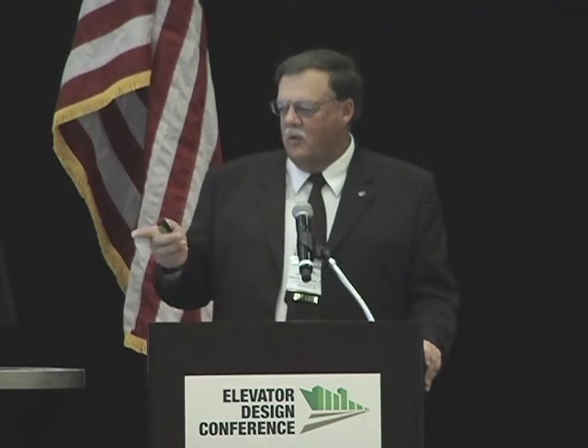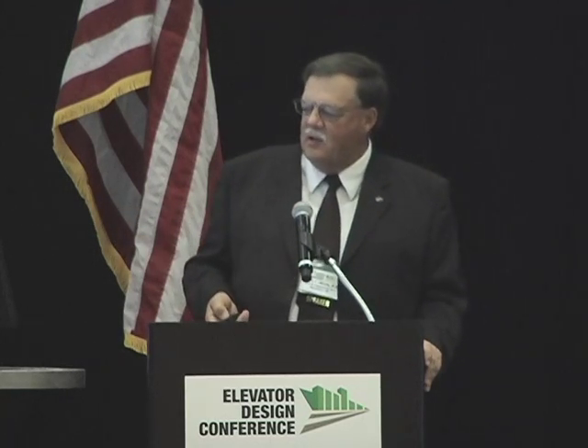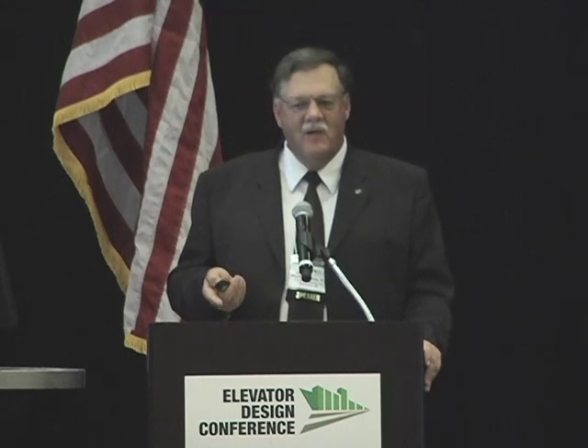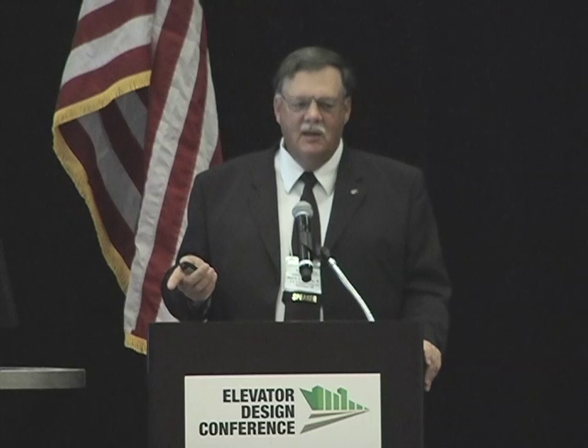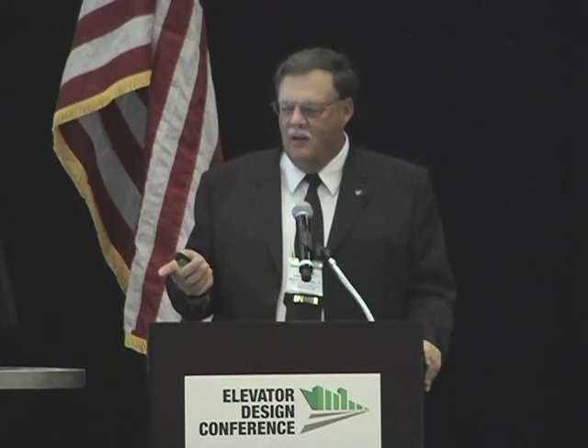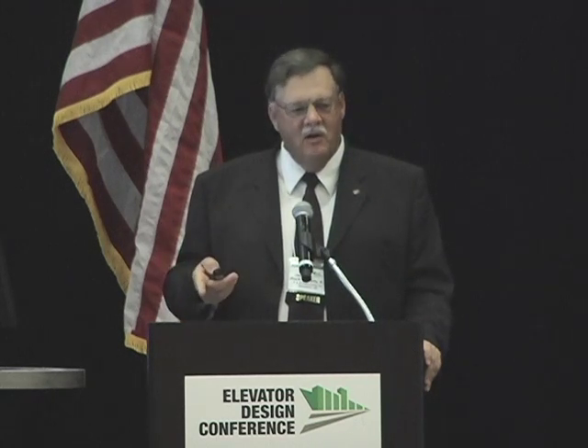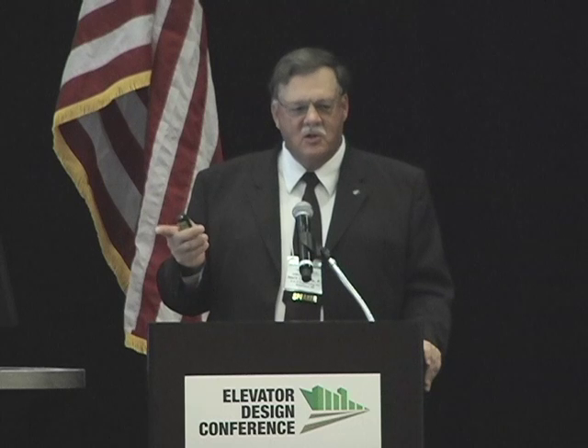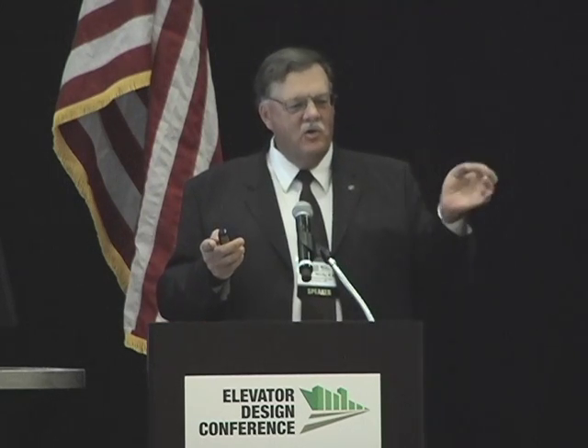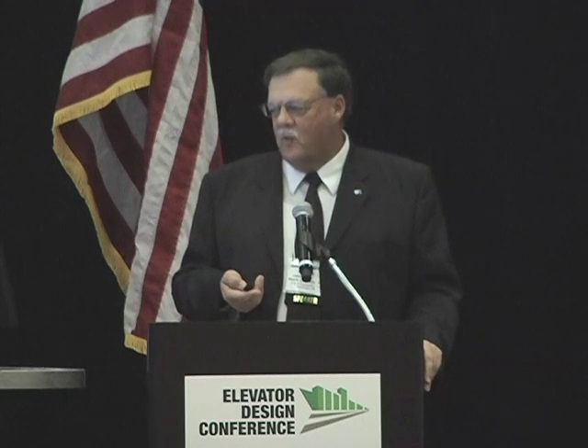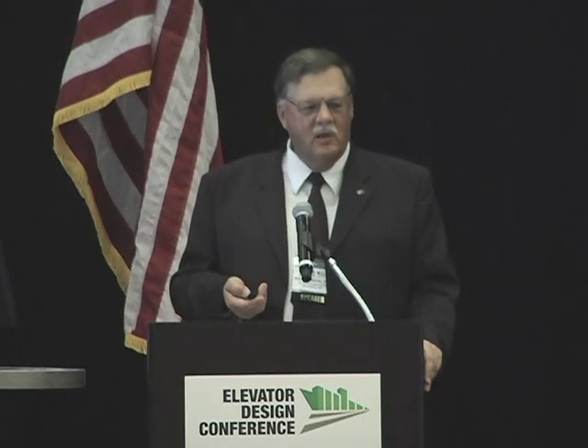Here's a picture of a standalone Siemens. There's a whole bunch of little switches on the upper right-hand side of that lower overload electronic relay for different functions you can turn on and off. And one of the standard features on that overload relay is ground fault. So you have a ground fault sensor built into your overload relay. Technically, it was a no-brainer to do that. What that gives you is, if there's a ground on your motor, the overload relay senses it and trips the starter instead of relying upon an upstream circuit breaker. Now you can coordinate a ground fault on a motor with your system so you don't take a breaker that takes out the entire MCC. So you can actually have staged ground fault systems right down to your motor starters with the electronic overload systems.